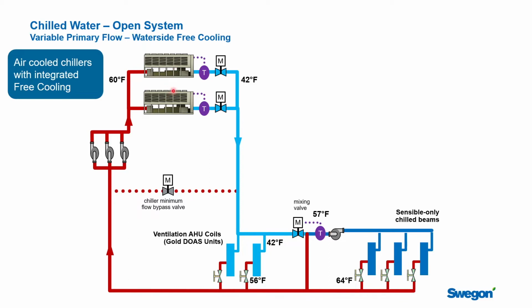If you're going to look at air-cooled chillers, this is actually a pretty straightforward thing to do. You can source air-cooled chillers that have integrated free cooling. There effectively is another coil in here that these fans would pull air across so that they could run the evaporator water through the water coils, cool that water down using the fans in the fan deck, and supply that back to the building without having to run the refrigeration to do that. In fact, a lot of them are smart enough to look at these loads in what we would call in series, so that we first try to cool the water down as much as we can by just running it through a coil and blowing air across it. And if we can't get it down to our supply water temperature, then what we would do is use some mechanical cooling to finish the job and get it down to 42 degrees. And all of that is in a packaged unit with package control, so it's very straightforward.